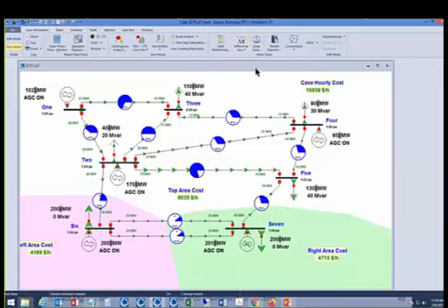What this does is it stores the current system state and the topology in your RAM memory. And then you can make a change to it and then compare the difference. So, for example, I'm going to click on this generator at bus 4, the little breaker symbol by it, and take it out of service, and then resolve the power flow.